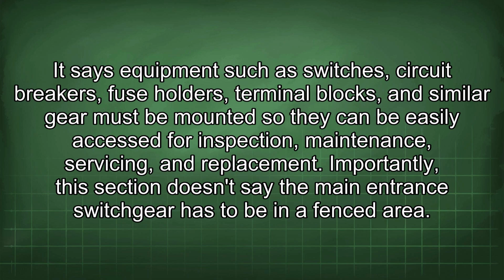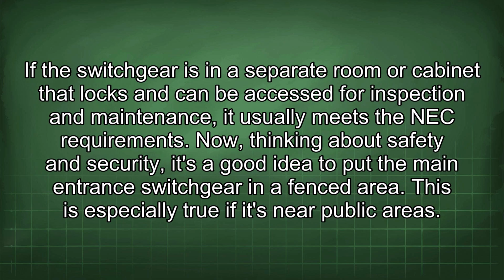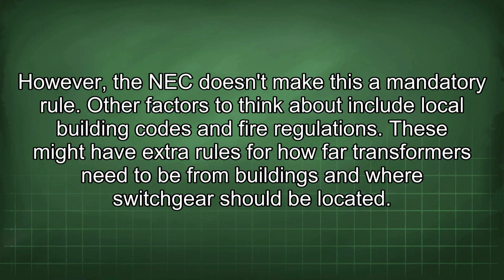Importantly, this section doesn't say the main entrance switchgear has to be in a fenced area. If the switchgear is in a separate room or cabinet that locks and can be accessed for inspection and maintenance, it usually meets the NEC requirements. Now, thinking about safety and security, it's a good idea to put the main entrance switchgear in a fenced area. This is especially true if it's near public areas. However, the NEC doesn't make this a mandatory rule.